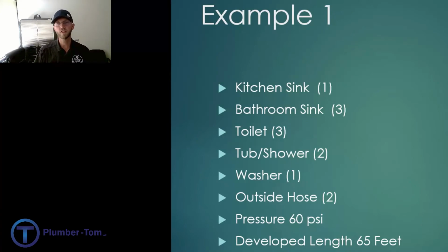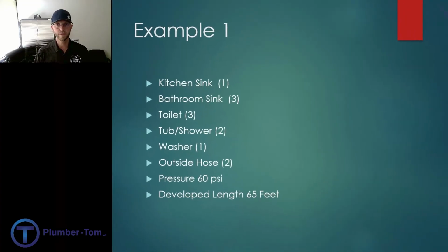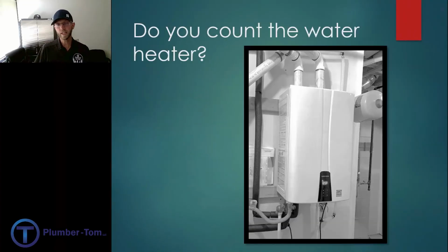We have the information that we need in order to size this. Question: do you include the water heater in your sizing? The answer is no. The water heater is just like pipe when it comes to water pipe systems. It just passes through there. So you don't have to add anything for a water heater.